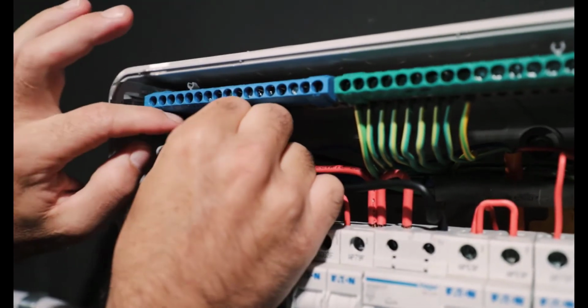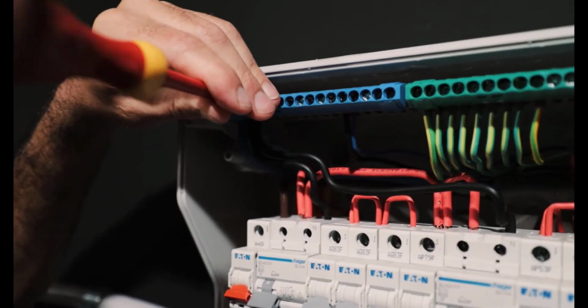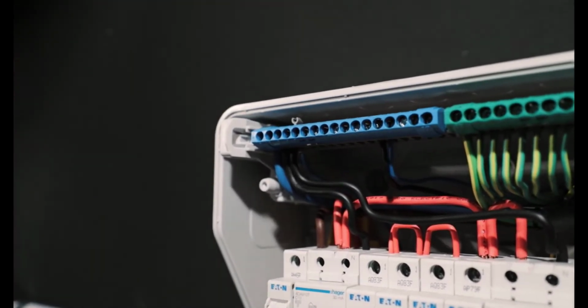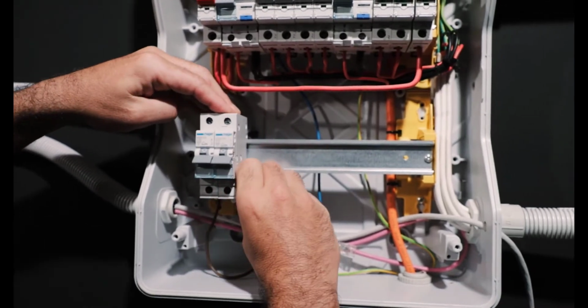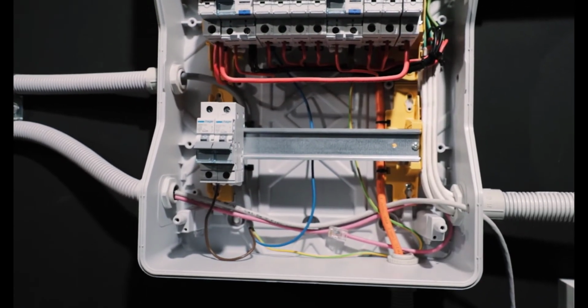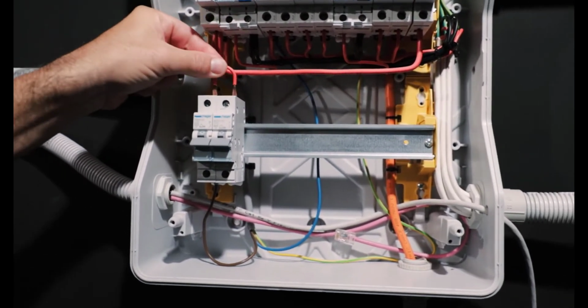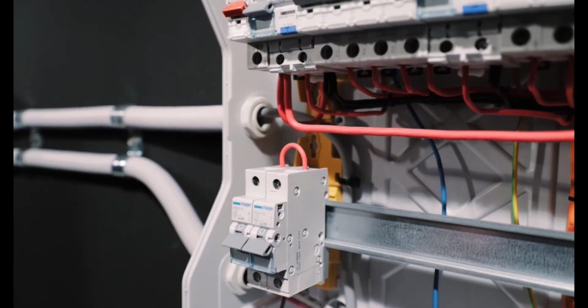The alternative, as per the previous video, is looking at grid measurement. That is looking at the power flow to and from the grid, and it's then calculating what's going on at the loads. In an ideal scenario, we'd always look at consumption measurement, because as I said, it's the most accurate.